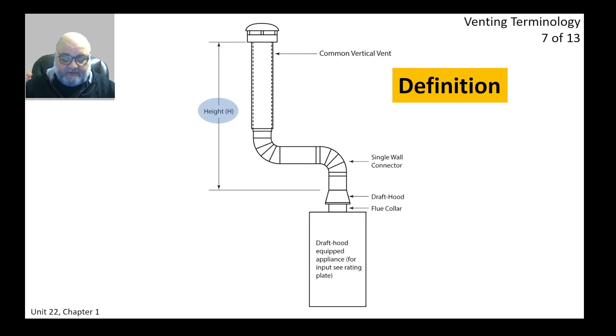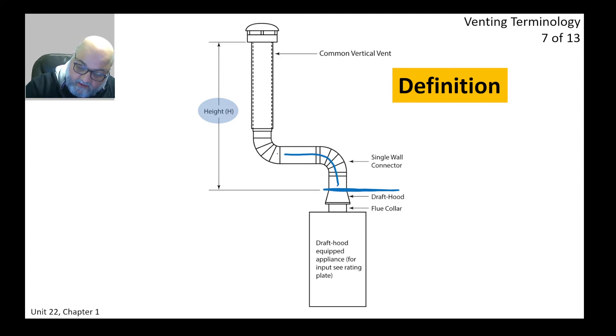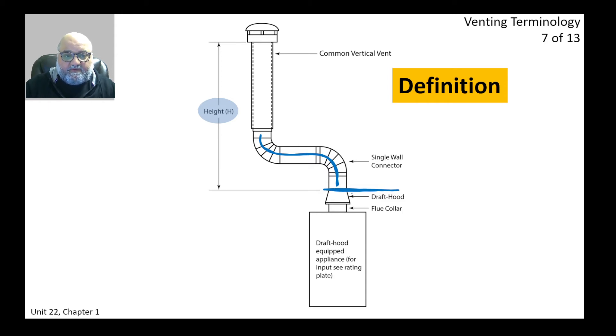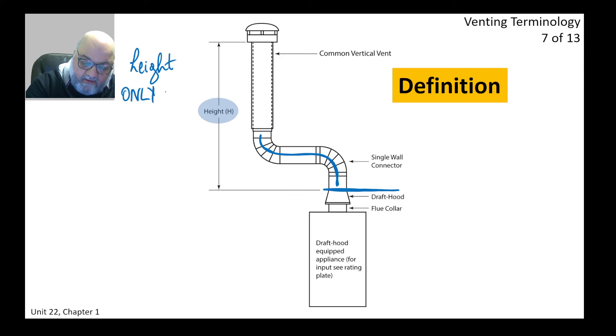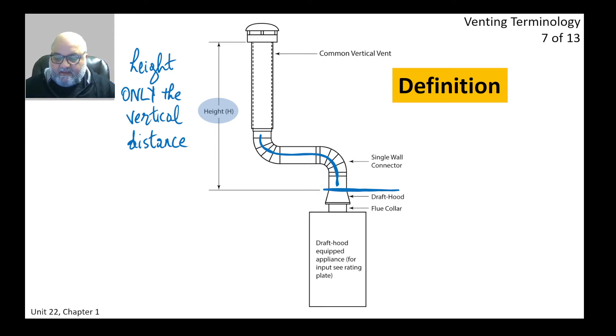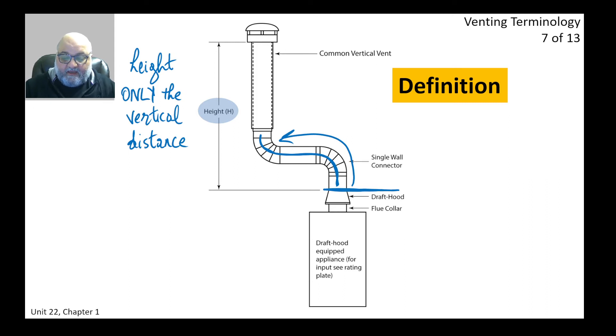The other important definition is stack height. For a single appliance, stack height is straightforward: it starts where the vent connector begins, all the way up to the termination in the atmosphere. H is the total height of the vent run. Remember: when we say height, we mean only the vertical distance — not any horizontal runs.